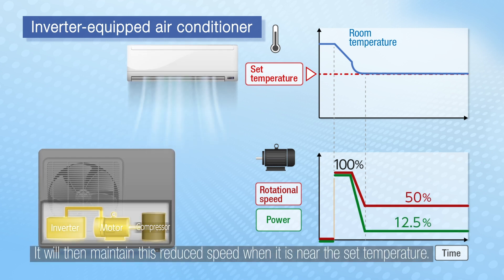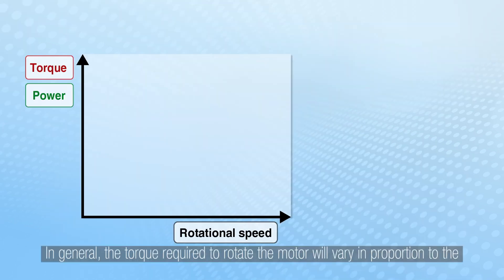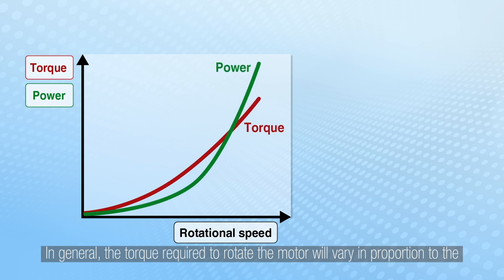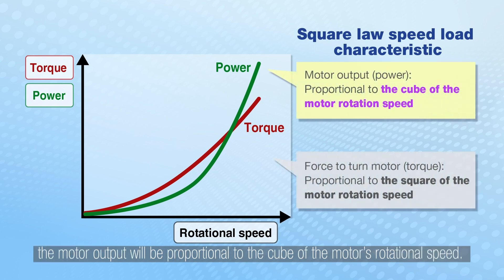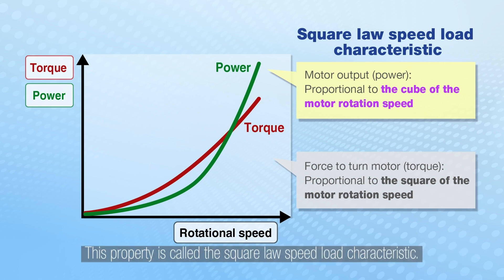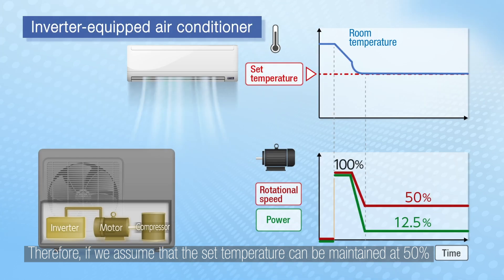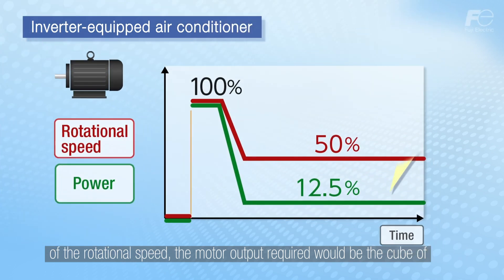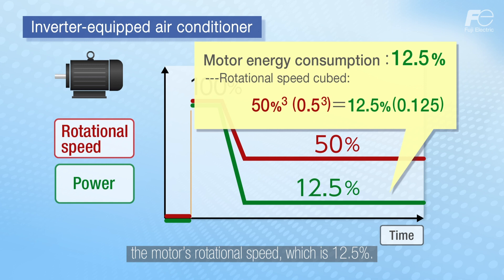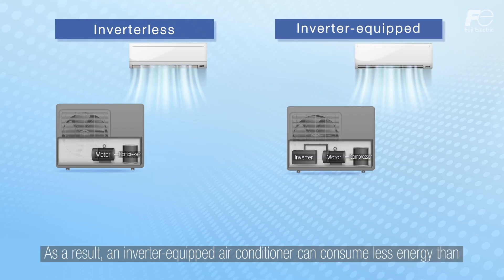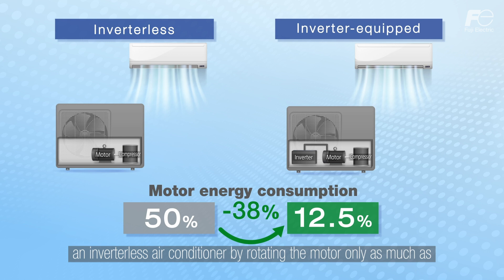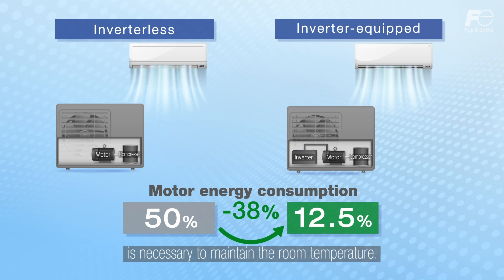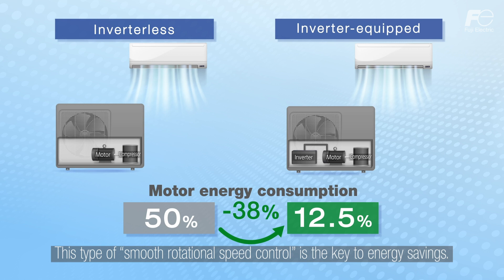The inverter will then maintain this reduced speed when near the set temperature. In general, the torque required to rotate the motor varies in proportion to the square of the motor's rotational speed, and the motor output is proportional to the cube of the motor's rotational speed. This property is called the square law speed-load characteristic. Therefore, if the set temperature can be maintained at 50% of the rotational speed, the motor output required would be the cube of 50%, which is 12.5%. As a result, an inverter-equipped air conditioner can consume less energy by rotating the motor only as much as is necessary to maintain the room temperature. This type of smooth rotational speed control is the key to energy savings.